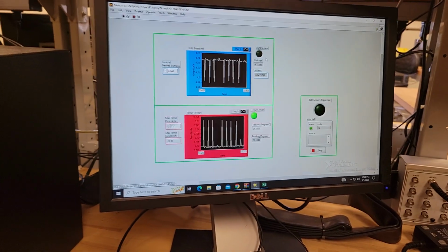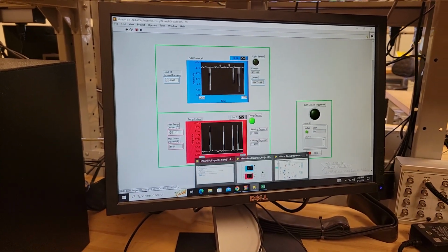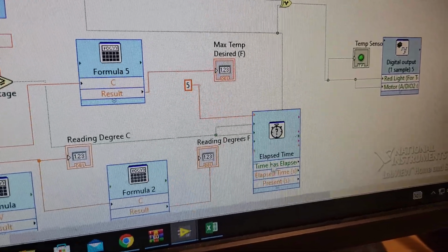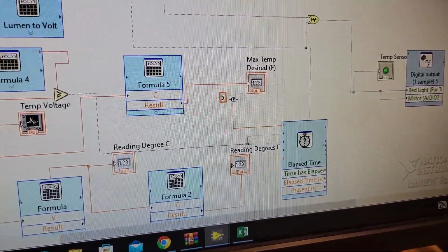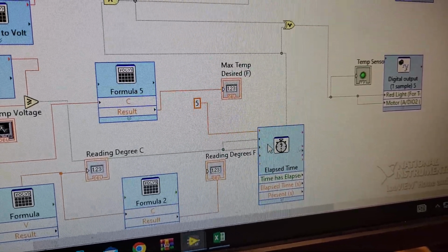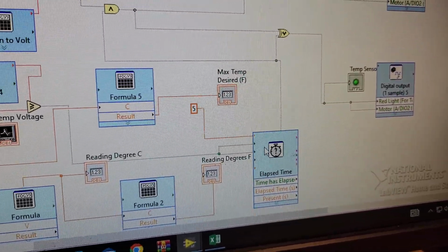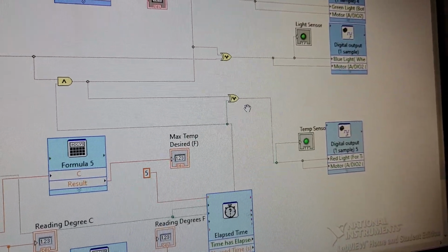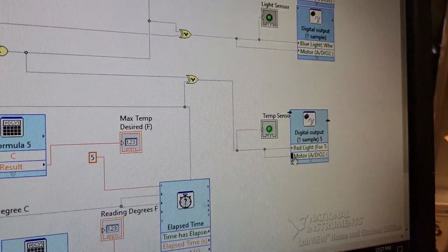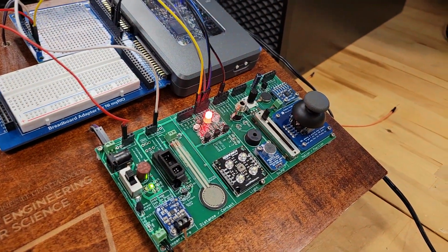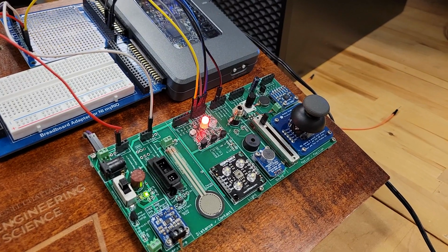Cole, if you can go ahead and switch us over to the on delay timer. We got it right down here. It's waiting on a specified time, 5 seconds of continuous true, and we could make that adjusted, but this is just for demonstration purposes. And then it's of course outputting to that exclusive OR gate, and then that determines if the sensor turns on or off.